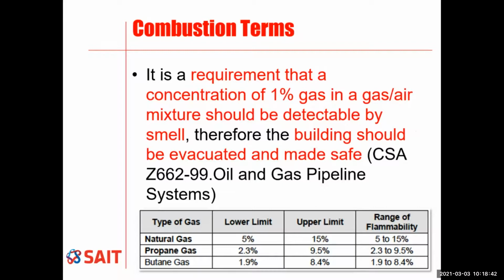Okay, so this is the smelling of gases. This is what they're talking about here: a requirement that a concentration of 1% gas be detected by a human nose, so to speak. So anytime you have a gas leak, you should evacuate. If you go into a building and you smell gas, your job is to get people out of the building and then investigate the gas leak, because you may be a source of ignition for that gas leak. Don't turn anything off, don't turn anything on, just get out.